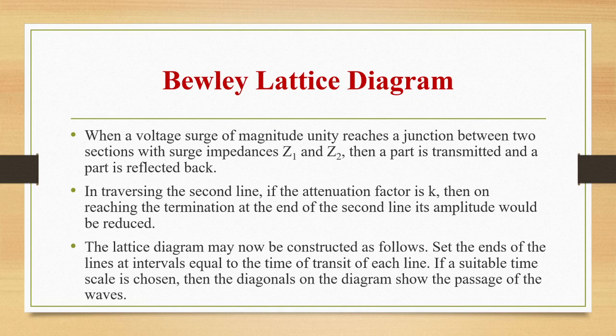The lattice diagram may be constructed as follows: set the ends of the lines at intervals equal to the time of transit of each line. If a suitable time scale is chosen, the diagonals on the diagram will show the passage of the waves. We consider surge impedances Z1 and Z2. Whenever a voltage surge of magnitude unity reaches a junction between two sections with surge impedances Z1 and Z2, a part will be transmitted and part reflected back.